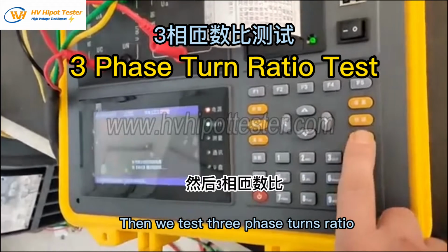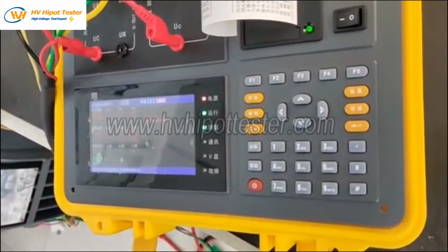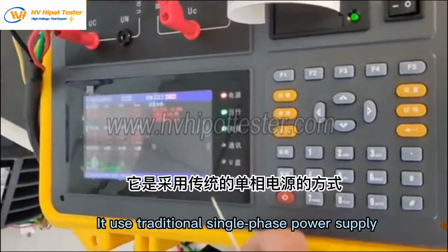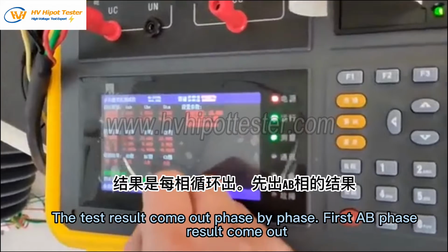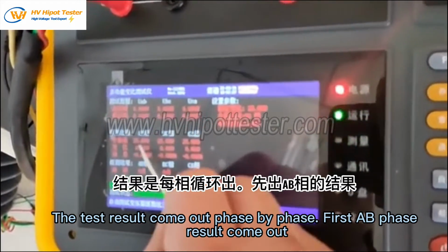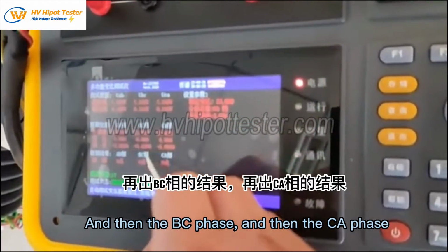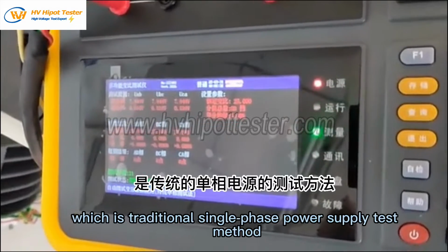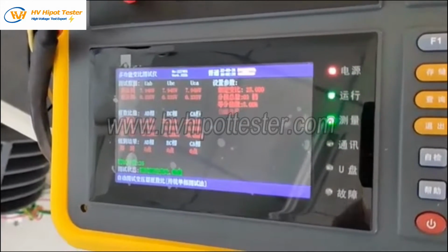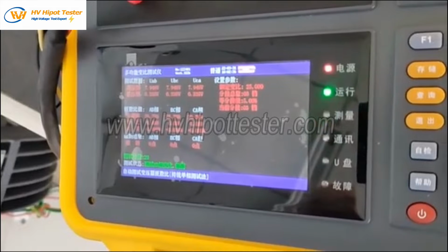Then we test three phase turns ratio. It used traditional single-phase power supply. The test result comes out phase by phase. First the AB phase result comes out, and then the BC phase, and then the CA phase, which is the traditional single-phase power supply test method.